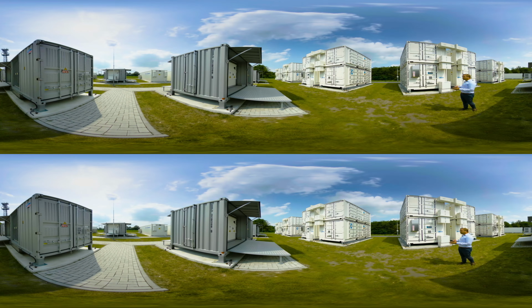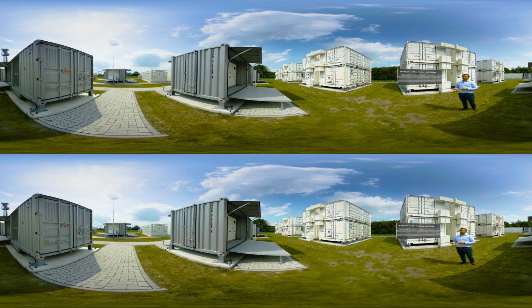The great advantage of this battery system is its large storage capacity — in numbers, 20 megawatt hours. With an output power of 4 megawatts, we need about 5 hours to fully charge or discharge the battery storage once.